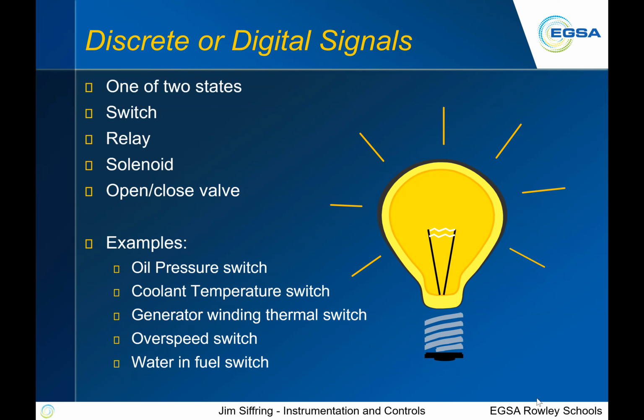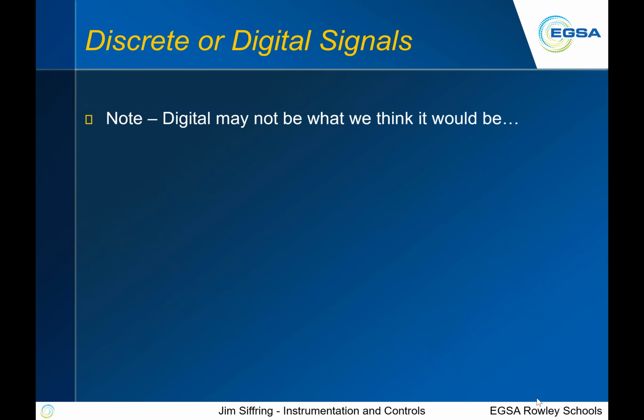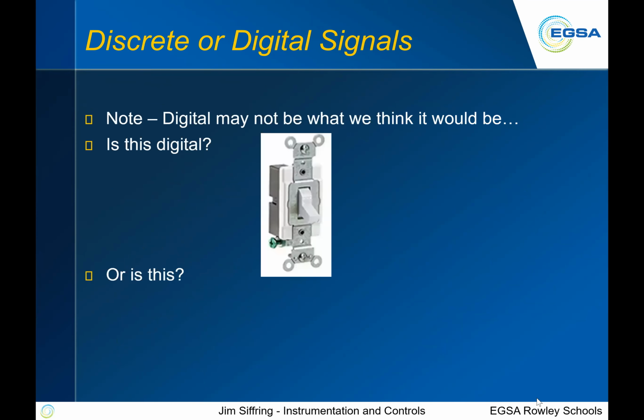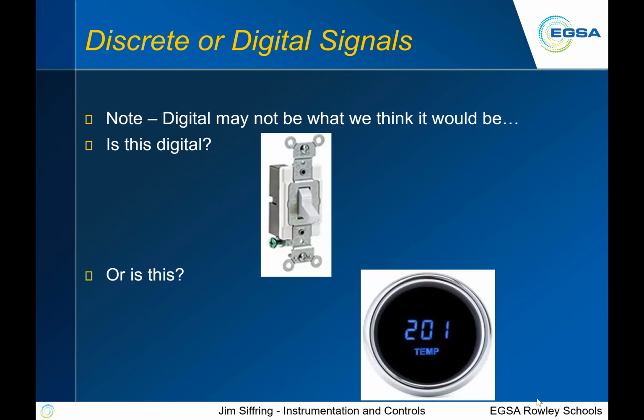So what is that? A switch, a relay, a solenoid, a valve that only closes or opens, as only two positions. Examples of that: a pressure switch, a temperature switch, thermal switches, overspeed switch, or maybe a water in fuel switch, something like that. Basically, it's on or off. And as a note, is this the digital device, or is this the device that's digital? Since I can't see any hands raising, I'll just say the switch itself is the digital device. It's on or off. It's one of those two positions.